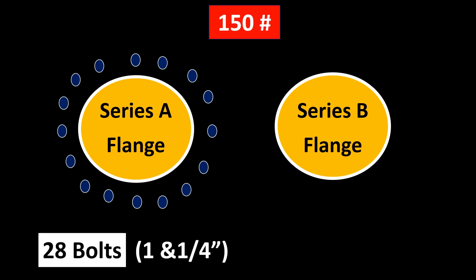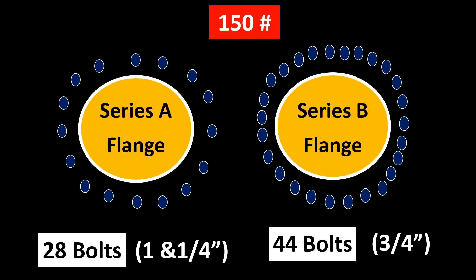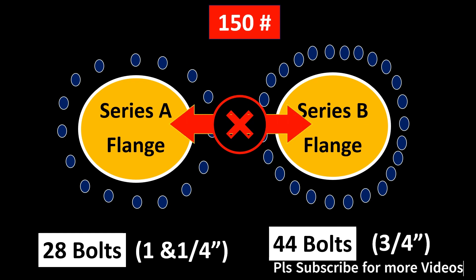But Series B flanges are actually having far more bolts, which is 44 bolts of 3/4 inch diameter. That means these two flanges will not mate with each other. So if instrumentation is selecting Series A flange and piping is selecting Series B flange, then they are not going to mate with each other.